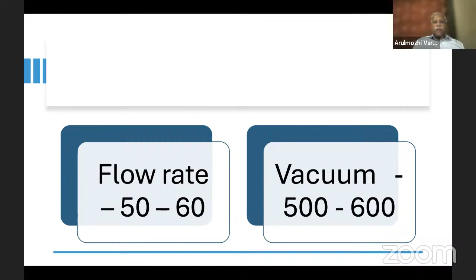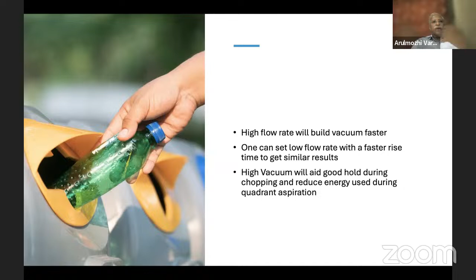So high flow rate, as I told you, will build vacuum faster. One can set a low flow rate with a faster rise time to get similar results. High vacuum will hold very well. The higher the vacuum, the better the hold, the easier the chop. With higher vacuum and a harder cataract, it will implode the piece into the phaco tip with lesser energy, giving you more efficiency. Very important, whether you do any of these techniques, that you do not have any wound leak.